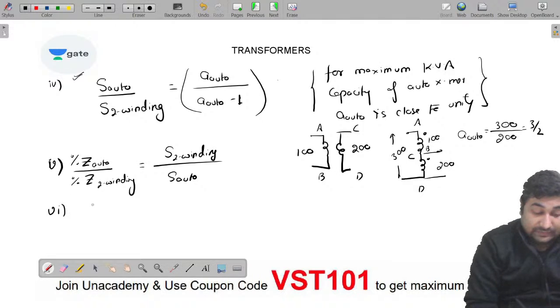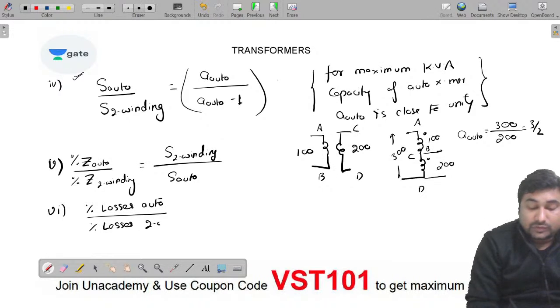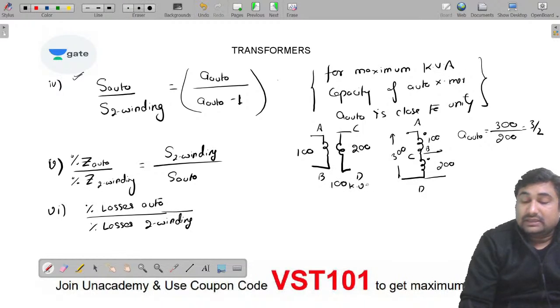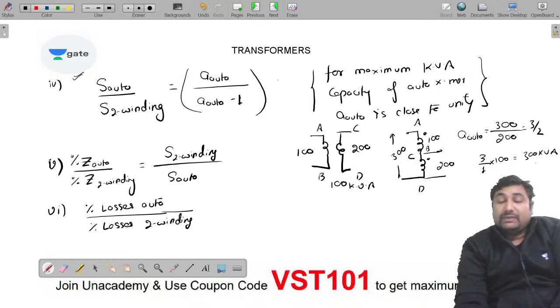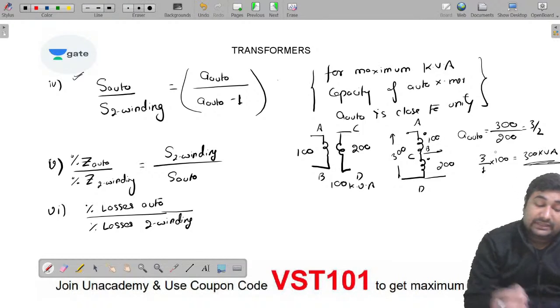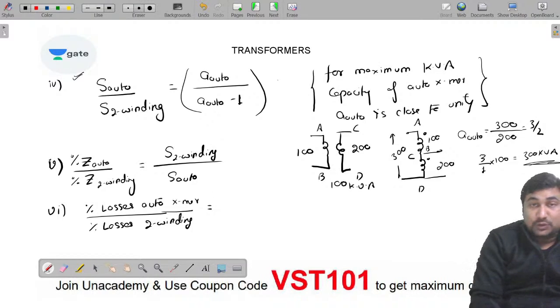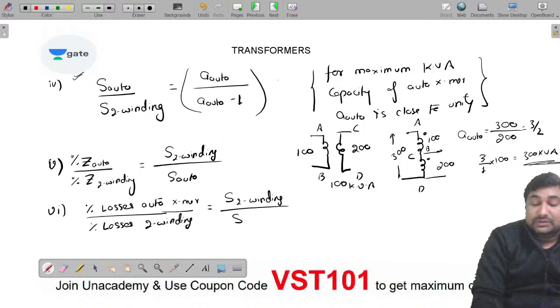One more thing you have to remember about the losses. Percentage losses when auto transformer is running at its rated, to percentage losses in case of two winding transformer when the two winding transformer is operating at its rated. Let us suppose this is of 100 kVA, then we can calculate the kVA capacity of this. That kVA capacity will become 3 by 1 into 100. So you can say, sir, 300 kVA. So if the auto transformer is operating at 300, and the two winding transformer is operating at 100, then look very carefully, beta: actual losses will remain the same. However, the per unit losses or percentage losses are different. That is kVA capacity of two winding to kVA capacity of auto transformer.